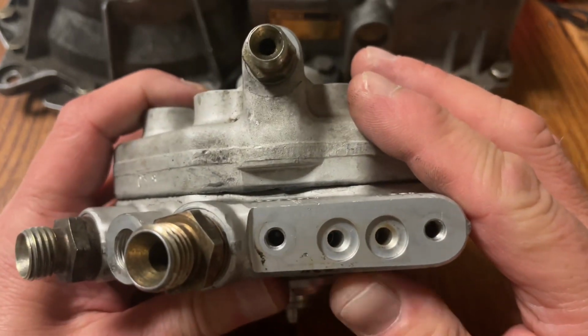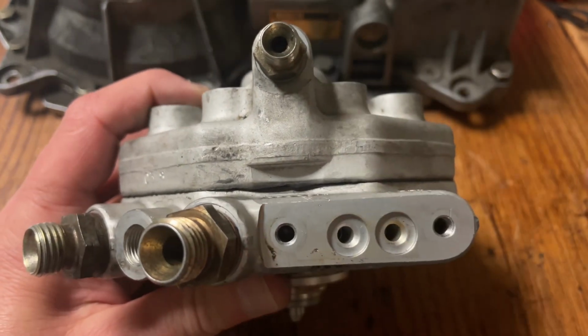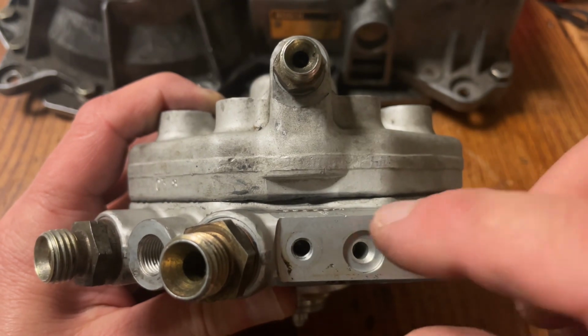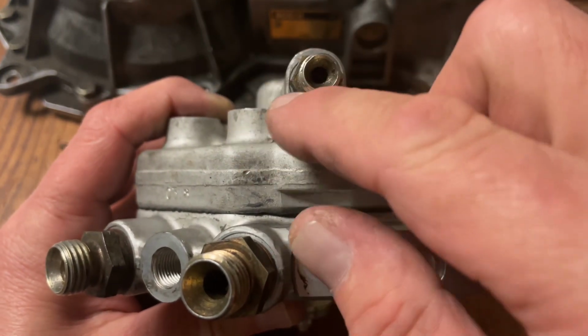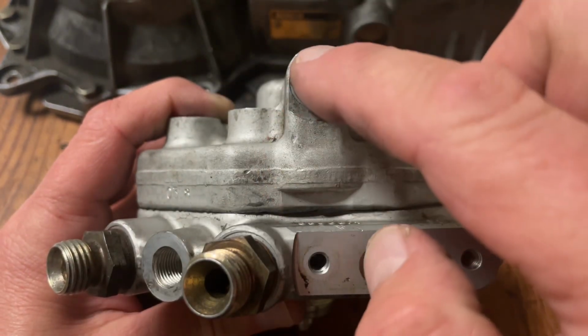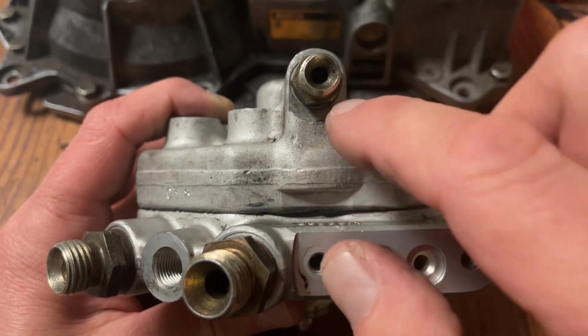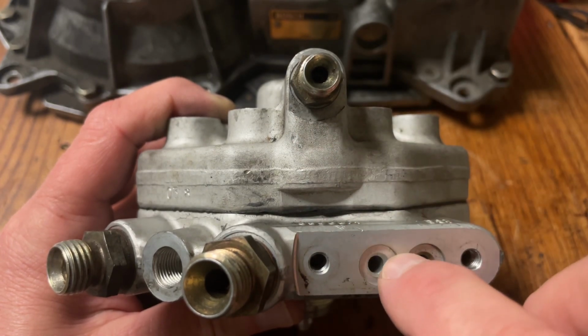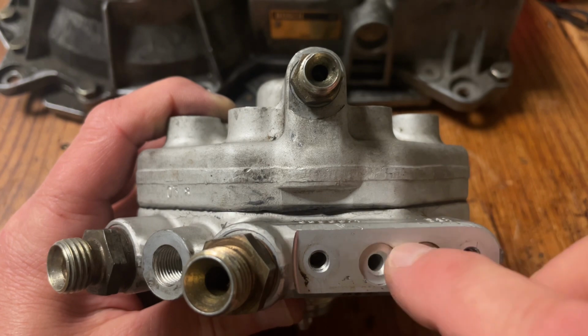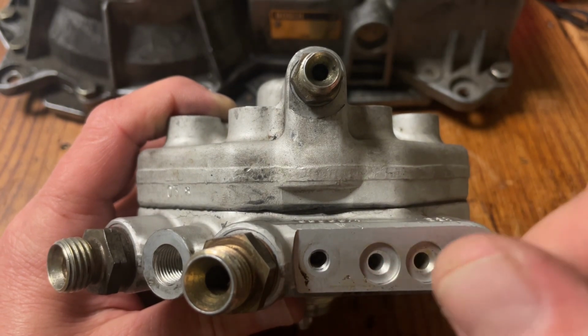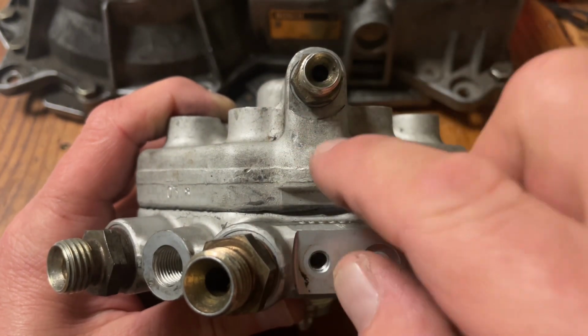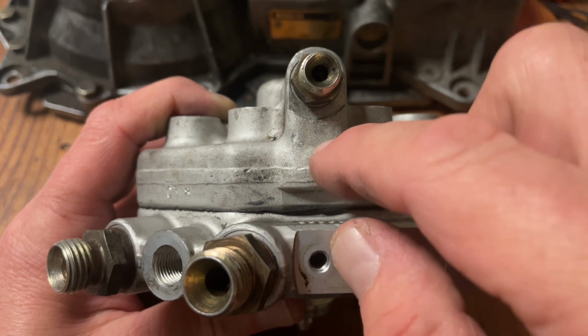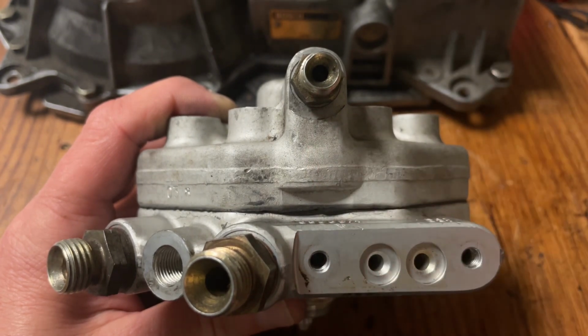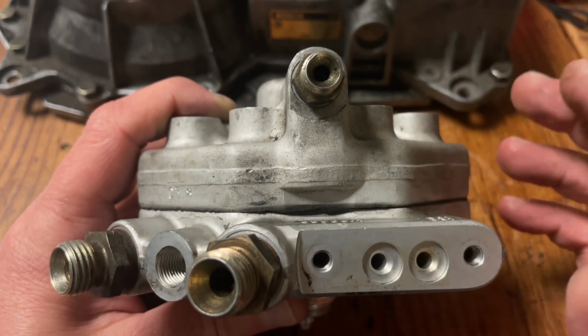And when the EHA valve is electrically connected, that set point of 0.4 bar difference between top chamber and lower, or upper chamber and lower chamber, is set via the set screw. By going counterclockwise, you can decrease the differential between the two, or you can increase this by going clockwise.